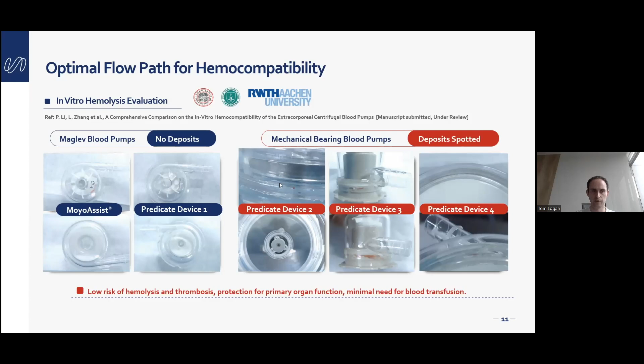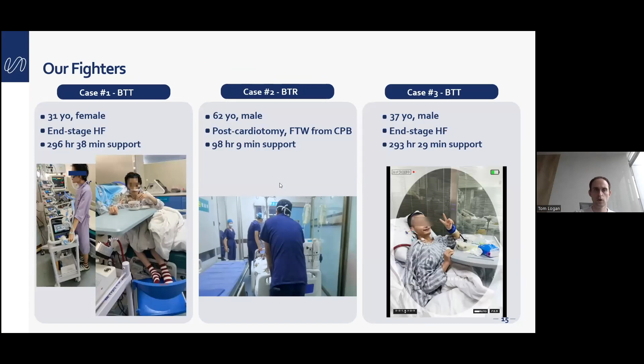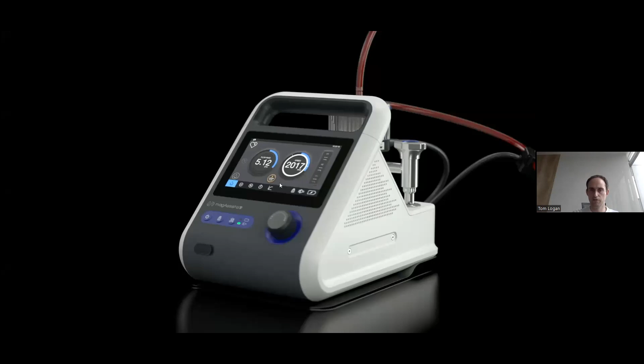And we have taken this through the clinical trial, mainly in China, and basically the clinical trial is complete, and we should be able to launch the product next year. So basically, building on the VAD, we have then developed an ECMO system. ECMO is extracorporeal membrane oxygenation. This is a technique where you take blood from the patient's venous system. It's passed through a pump and then through a membrane oxygenator to oxygenate the blood, and then put back either into the arterial system or into the venous system, depending on your objectives in the ECMO treatment. And if you put the blood back into the arterial system, you can also increase the blood flow. That's usually the most popular method.